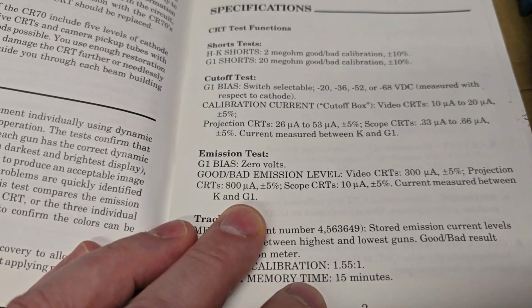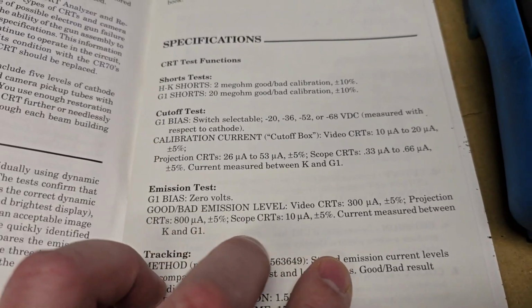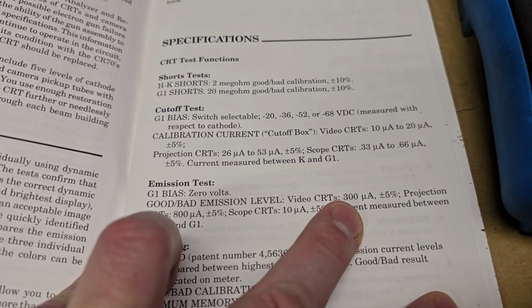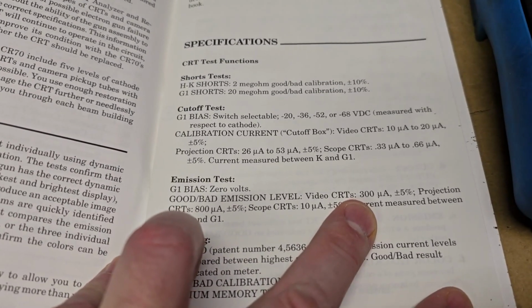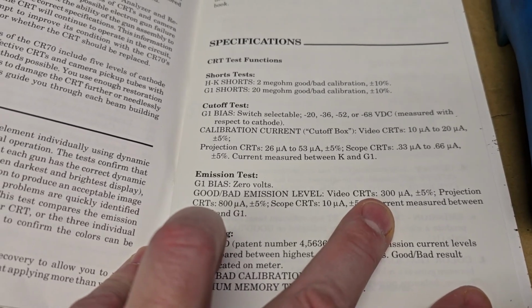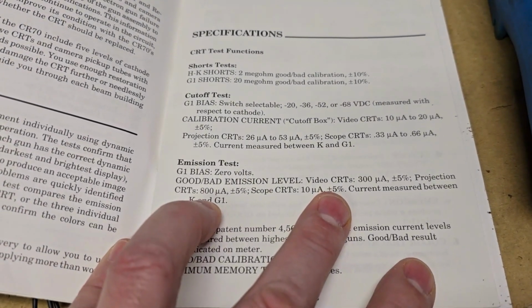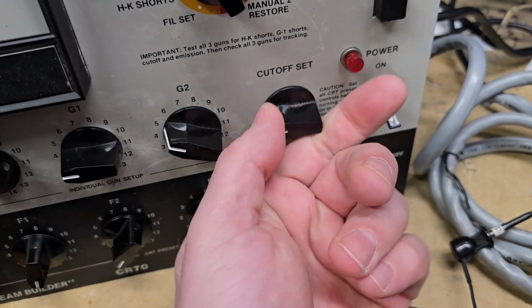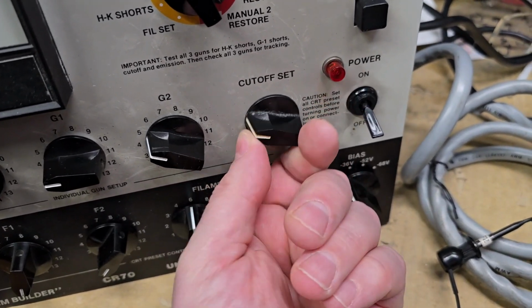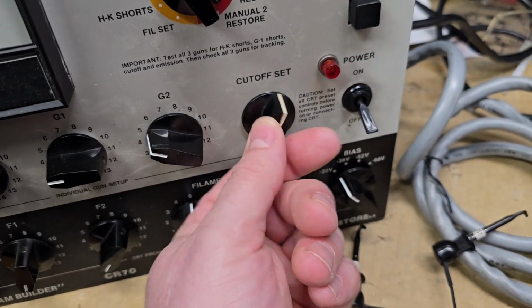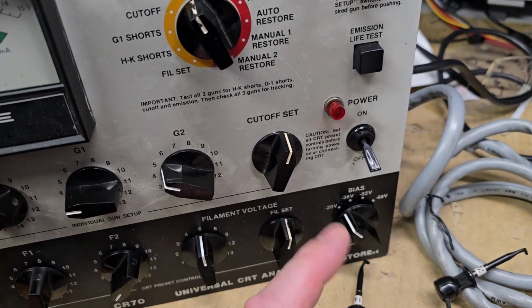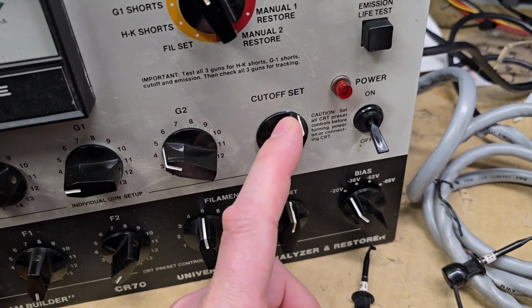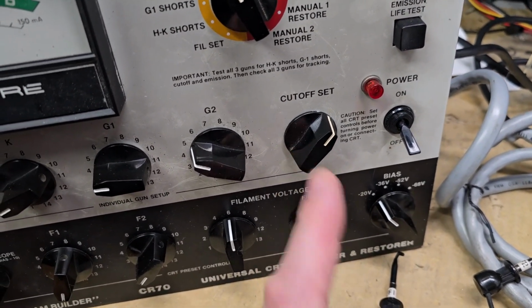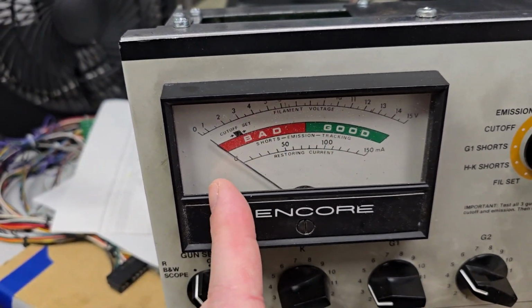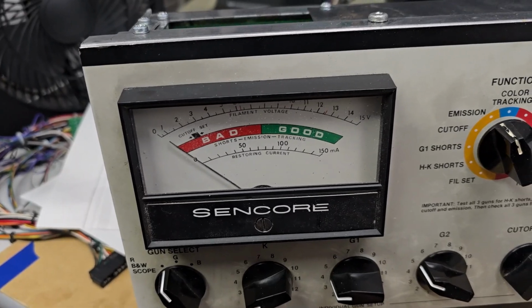And I tried testing it, and I can't get anything on there. What I did do is, how would I get 300 microamps of load on the G2 line? And I did my ohm calculator and a 1 mega ohm resistor at 300 volts. And usually this cutoff set here will set G2 voltage between like 0 and 400 and something volts. Usually, I'm pretty sure. I'll test that real quick for you. So if I put a 1 mega ohm load at 300 volts, I should have 300 microamps, and my meter should read between bad and good right in the center line. Hopefully that's making some sense.